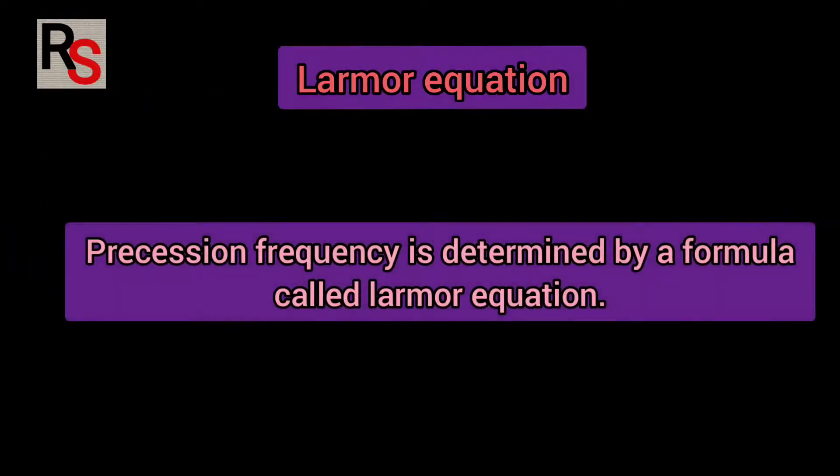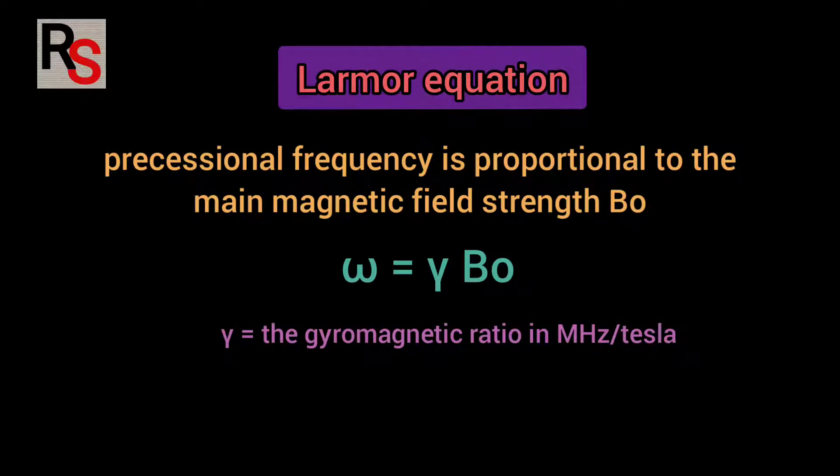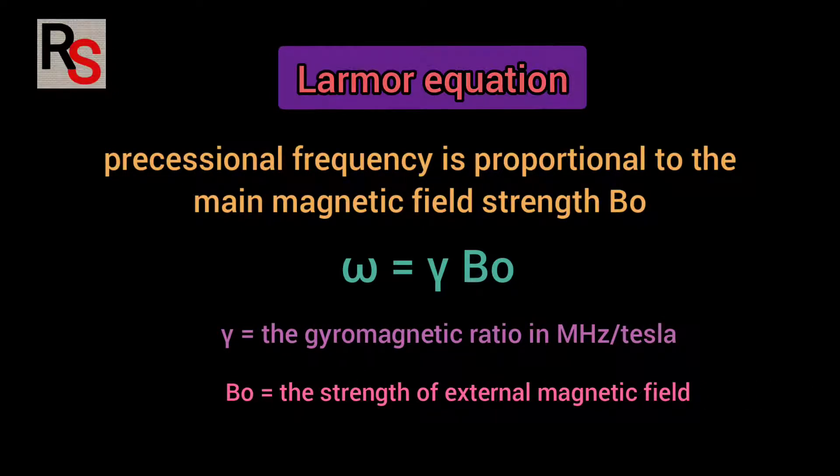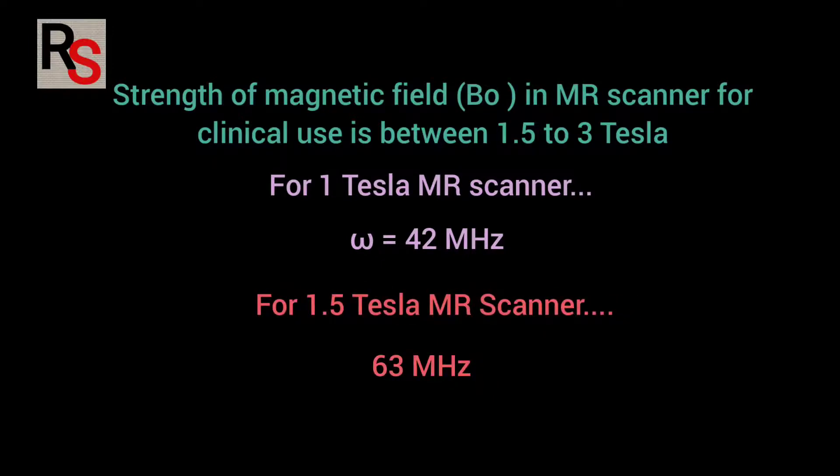The precession frequency omega is determined by a formula called Larmor equation which states that precession frequency is equal to gamma multiplied by B0 where gamma is gyromagnetic constant and B0 is the strength of external magnetic field. The majority of MR systems in clinical use are between 1.5 to 3 Tesla. So for field strength of 1 Tesla the precession frequency of hydrogen is 42 megahertz or 42 million cycles per second and 63 megahertz for 1.5 Tesla scanner.